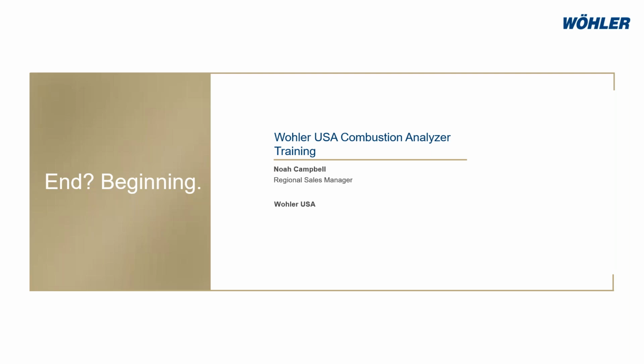A question was, on my A550, I only see CO high and COC readings, and COC is always a higher ppm. Right, COC is carbon monoxide corrected, so it will always be a higher reading. CO corrected is a reading without the influence of oxygen. And like I said before, if you don't need the COC, you can delete it off your setup window. But I do recommend it. It's helpful when you're testing, because you can identify what your reading would look like without the influence of oxygen.